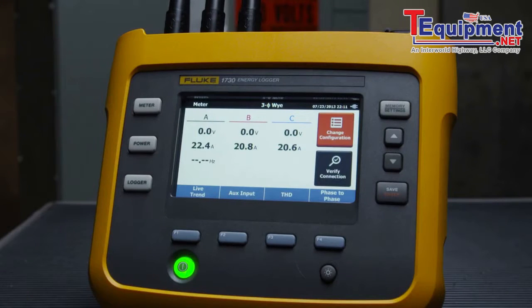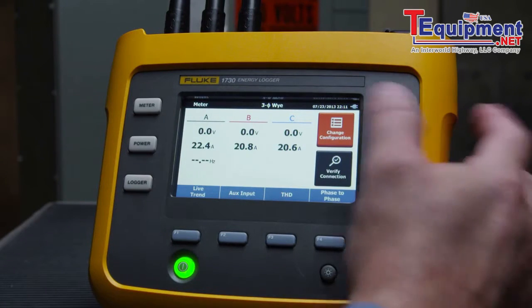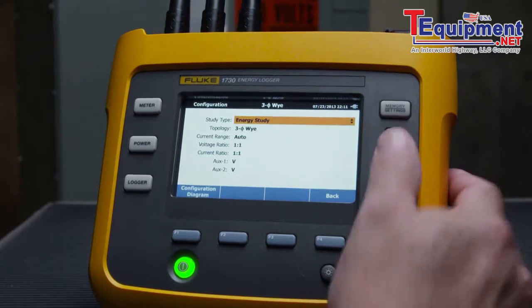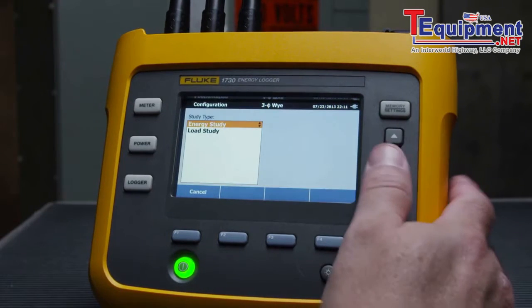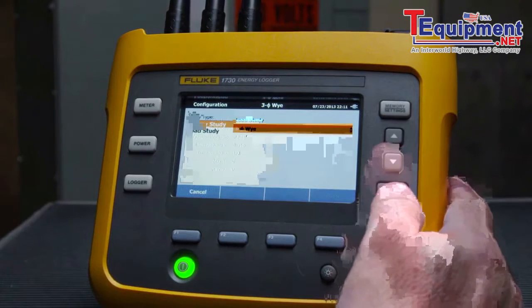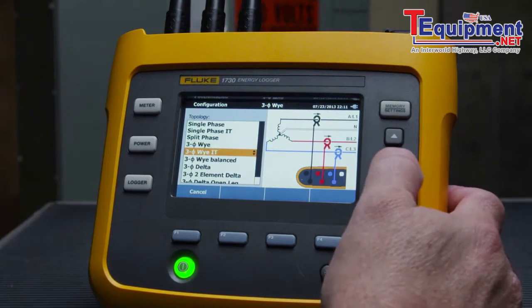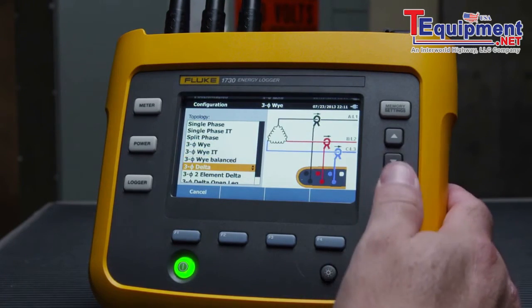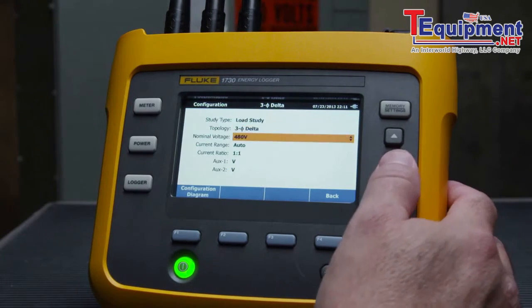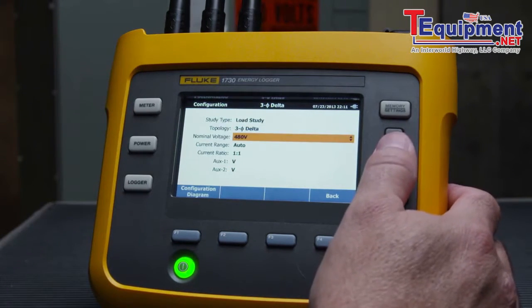To perform a load study, start in the meter screen, select Change Configuration, and choose Load Study under the study type. Select your circuit type from the list.